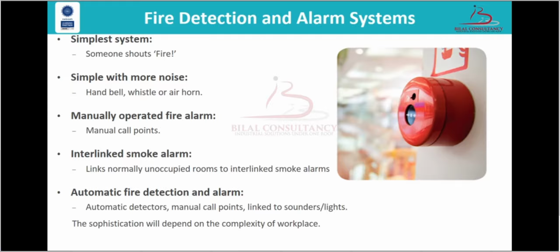Automatic fire detection and alarm. This system is made up of automatic detectors and manual call points linked into a central control box, linked in turn to sounders and or lights. If a person sees the fire, they can activate a manual call point and raise the alarm. If there is no person present, then the automatic detectors will activate the system and raise the alarm. This type of system is commonly used to protect medium to high risk workplaces, multi-story buildings, and workplaces where sleeping accommodation is provided, such as care homes.